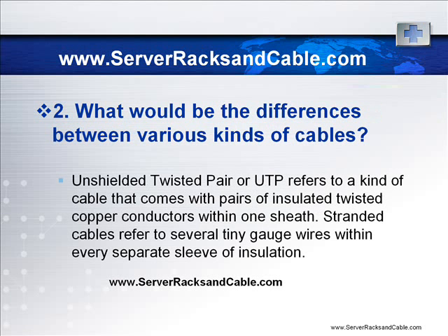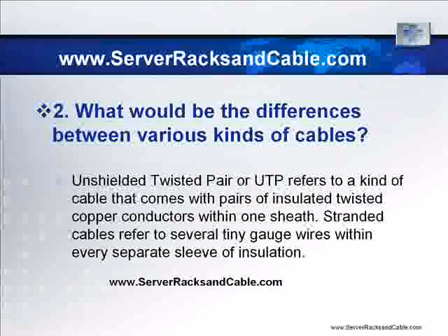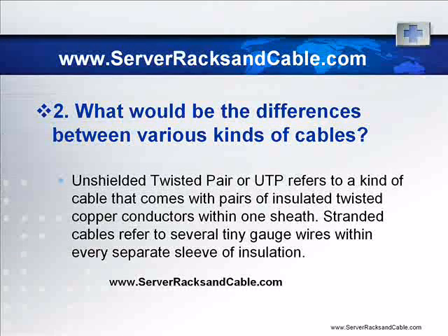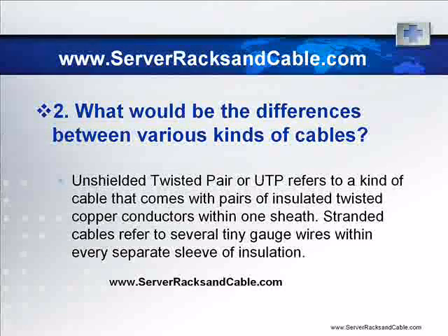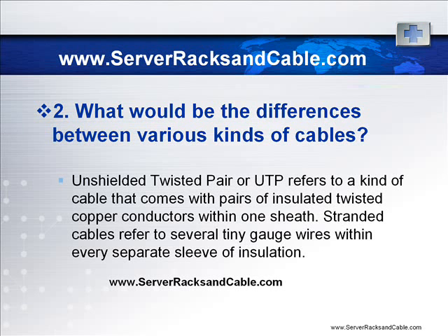What would be the differences between various kinds of cables? Unshielded twisted pair, or UTP, refers to a kind of cable that comes with pairs of insulated twisted copper conductors within one sheath. Cables of UTP are highly common when it comes to desktop communications, applications, and cabling. Stranded cables refer to several tiny gauge wires within every separate sleeve of insulation. Stranded cables happen to be more flexible, so they would be ideal for shorter distances, like patch cords. Solid cables have bigger gauge wires within every sleeve, and have improved electrical performance compared to stranded cables. They are traditionally used for inner walls, ceilings, and any kind of long cable runs.